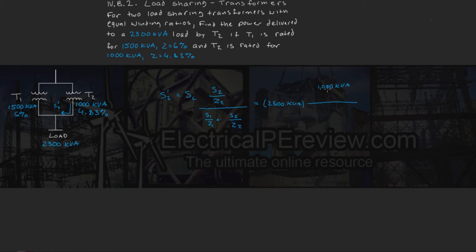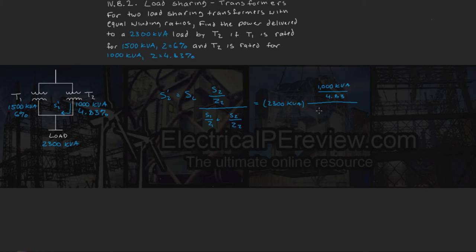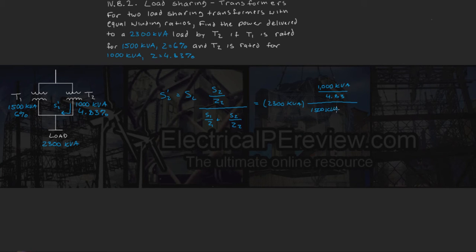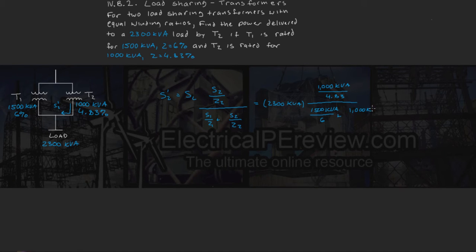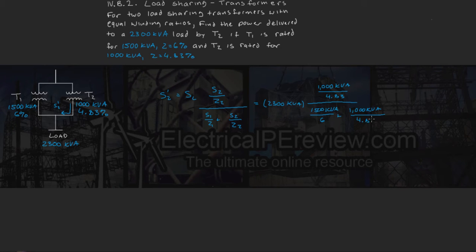And then on the bottom, we've got S1 is 1500 kVA divided by 6% impedance plus 1000 kVA divided by the same 4.83% impedance.